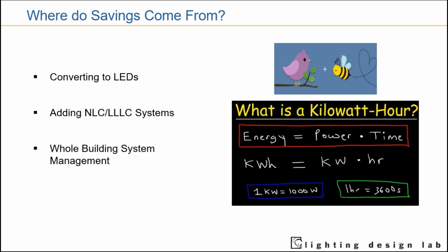So network lighting control systems, and connected lighting overall, will have a couple of solid benefits. If you have a legacy light source, be it fluorescent, metal halide, or incandescent, and you convert to LED, you are straight reducing the wattage. Great for savings. Adding your network lighting control systems, or luminaire level lighting control systems, will do both. They will reduce power, by implementing strategies we'll discuss later, like high-end trim or daylight harvesting, or they're going to reduce the time that the lights are on, be it by scheduling, occupancy, or vacancy, among other strategies. And when building management systems communicate with a network lighting control system for further efficiencies, or a system leverages the lighting sensors to tell an HVAC to lay off of its temperature settings, even more energy can be saved.